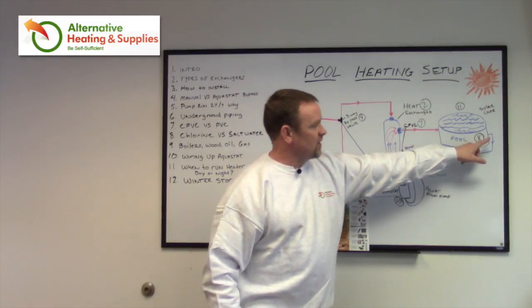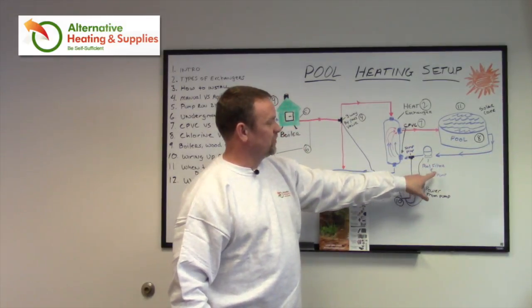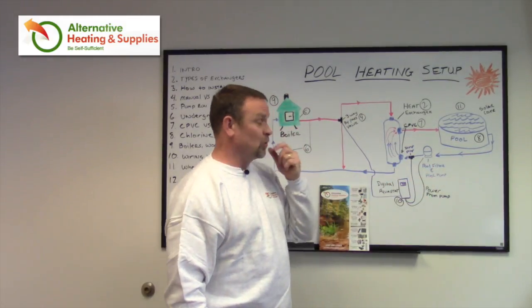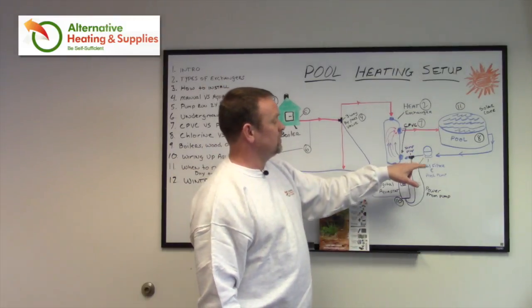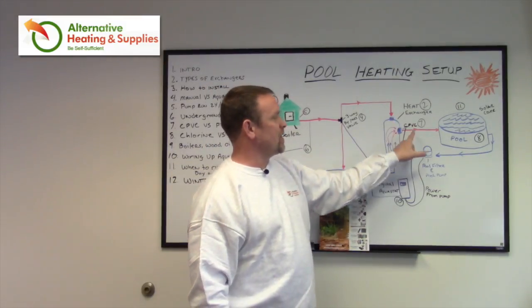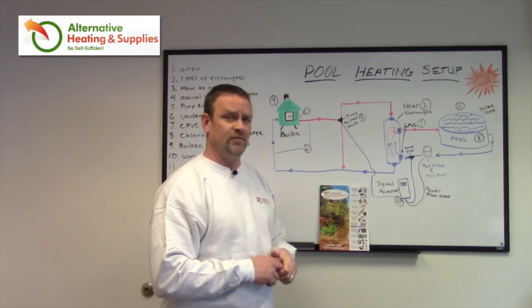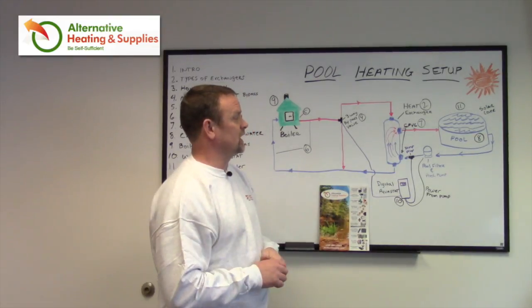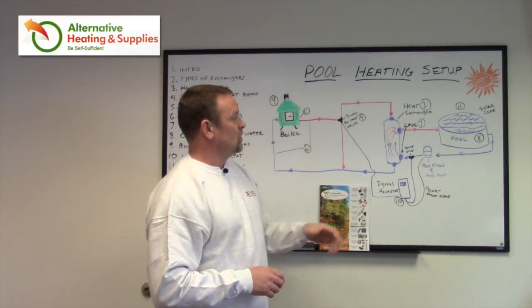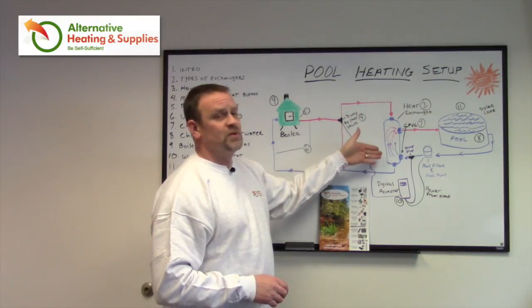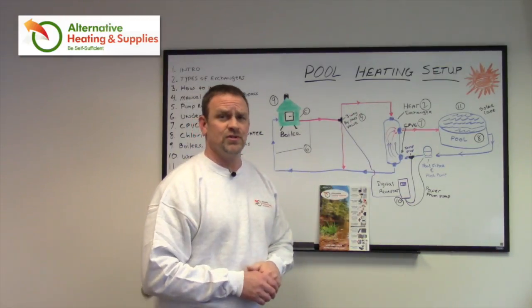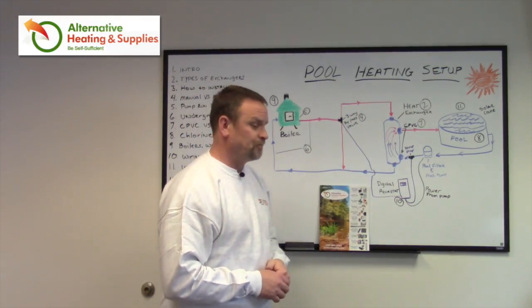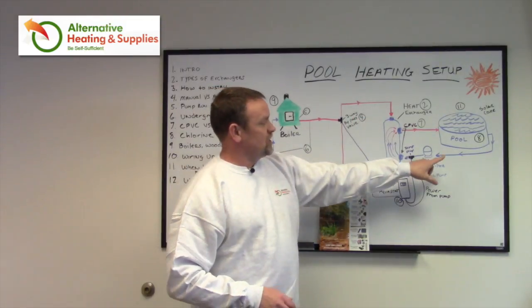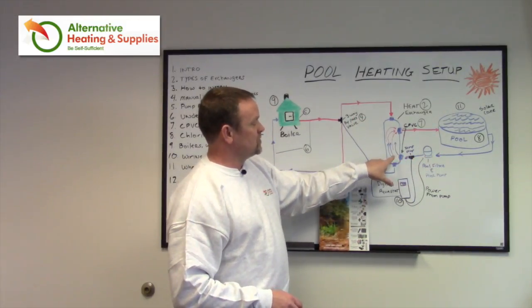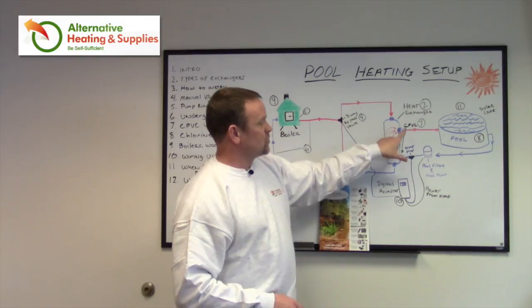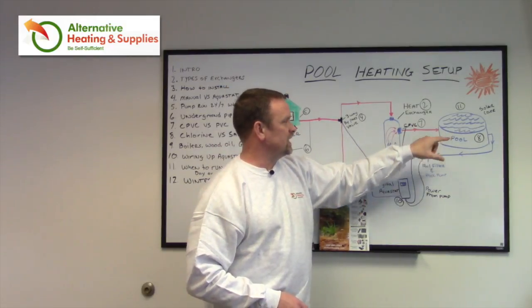The water comes out of the pool and goes generally to the pool filter and the pool pump. Before you had a heating system, it would go right back to the pool to be filtered and keep the water circulating. In this case, this is where you add your tube and shell heat exchanger, or whatever heat exchanger you decide, but we recommend the tube and shell. The water comes in, goes into the heat exchanger, and goes back out to the pool after it's been reheated.